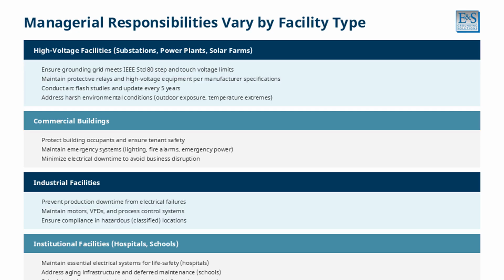Managerial responsibilities vary significantly by facility type. For high-voltage facilities including substations, power plants, and solar farms, ensure grounding grids meet IEEE Standard 80 step and touch voltage limits. Maintain protective relays and high-voltage equipment per manufacturer specifications. Conduct arc flash studies updated every 5 years, and address harsh environmental conditions.